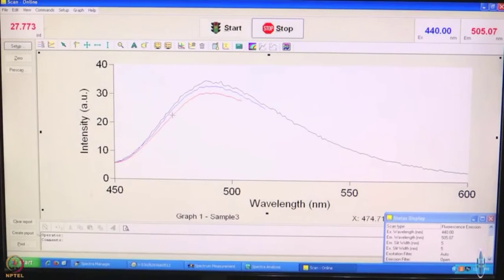All right. So, we have given it several minutes, and this is the spectrum that we have got so far. Now you see, we will not record the entire spectrum, because the point we are trying to make can be made with this data. If you go from the first spectrum to the second spectrum, there is improvement. If you go from the second spectrum to the third spectrum, when we increase the integration time from 1.5 seconds to 5 seconds, there is still some improvement. If you keep on increasing the integration time, some improvement or the other is going to come, but the question is, when will you stop?